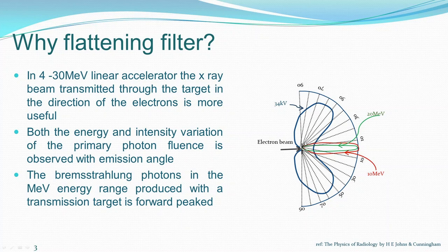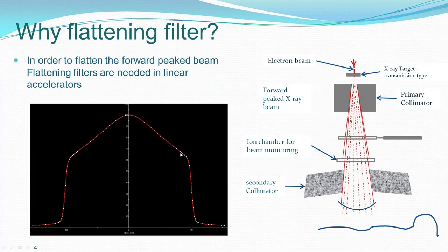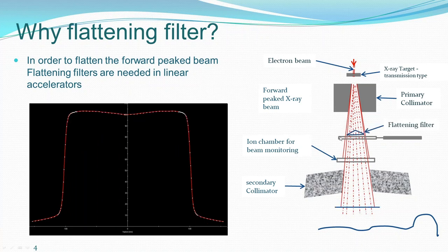When an electron beam of high energy impinges on a transmission target, most of the X-rays — the Bremsstrahlung produced — go in the forward direction. But for low energy photons, it goes at a particular lateral angle. So the final composite profile is something like what we get now for Triple F beams. The idea in those days was to give a uniform dose distribution, so they introduced a flattening filter between the target and the chamber.